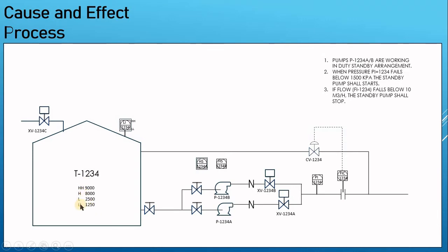The P&ID shows the tank with level values labeled L, L-L, H, and H-H — meaning low, low-low, high, and high-high values for the tank level. When the level goes below the low-low level, you will stop the two pumps to avoid cavitation — that's obvious — but you may need to do something else. From this P&ID we know they wanted to trip those two pumps. After the I&C guys do the cause and effect, they send it to the process team to evaluate, and they agree, add, subtract, or change things, because I&C is serving the process.